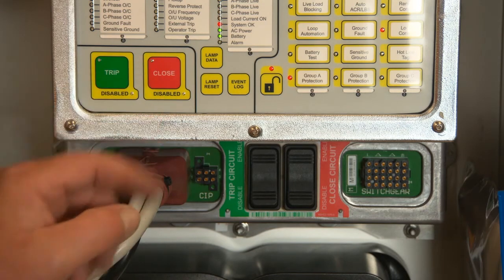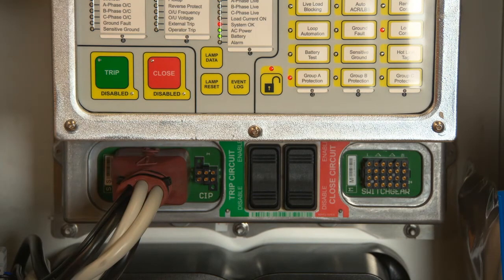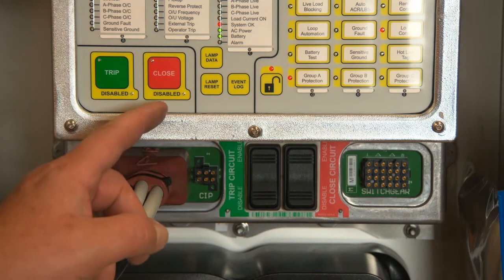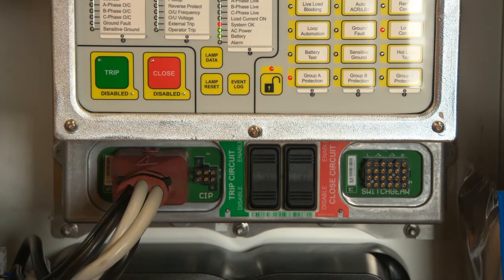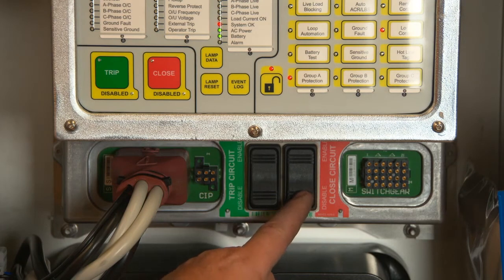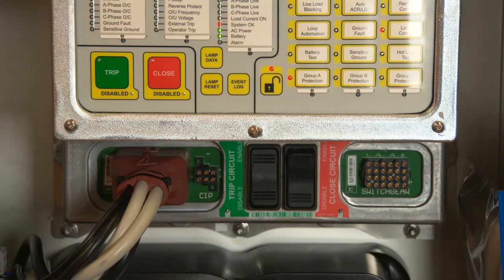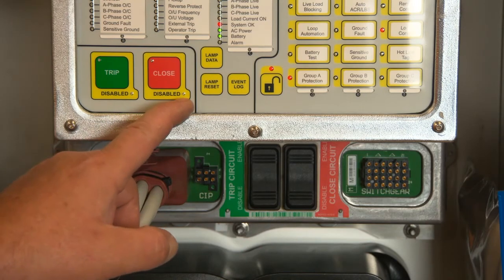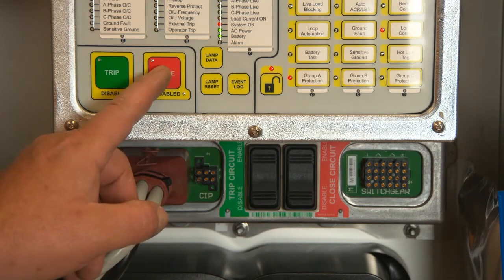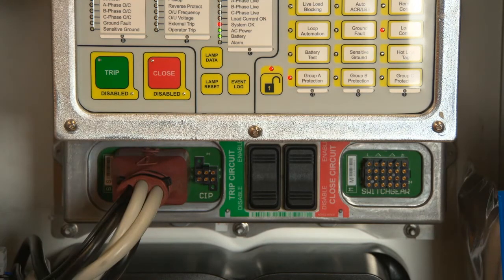Close button. If the recloser is closed, the LED in the top left corner will illuminate. Below is the disabled indicator. To disable the close feature, press the Disable Close Circuit button. This unit is now unable to close. In order to close this unit, press the Enable Close Circuit button below. The disabled indicator here will turn off. You can now close the unit.